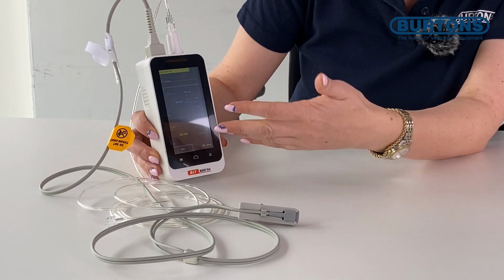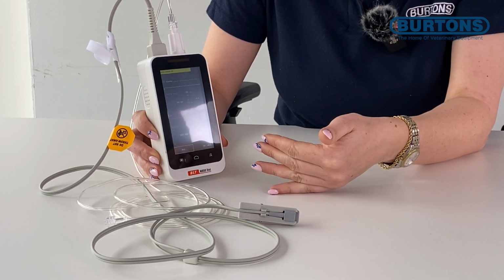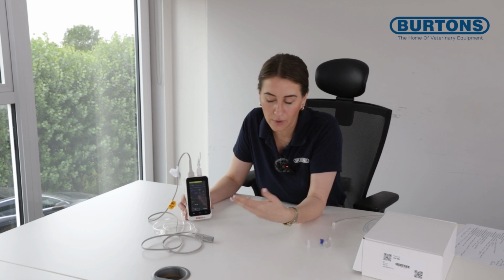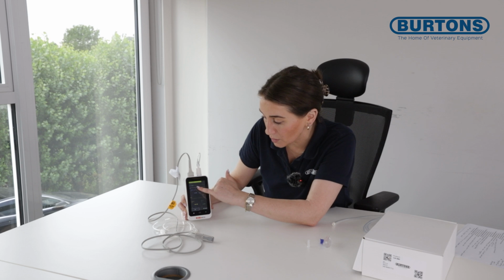So very briefly, end-tidal CO2 is measuring the percentage of carbon dioxide in a patient's exhaled breath, and fractional inspired is measuring the level of CO2 in the fresh gas flow or the inhaled portion of the patient's breathing. We can have issues with high fractional inspired, so it's important to try and monitor that. For example, exhausted soda lime, where the CO2 is no longer being absorbed by the soda lime, that fractional inspired CO2 will come up, and then that will be represented on our waveform with a non-return to baseline. So we'll get a graph that doesn't return to the zero baseline and with an increased fractional inspired.